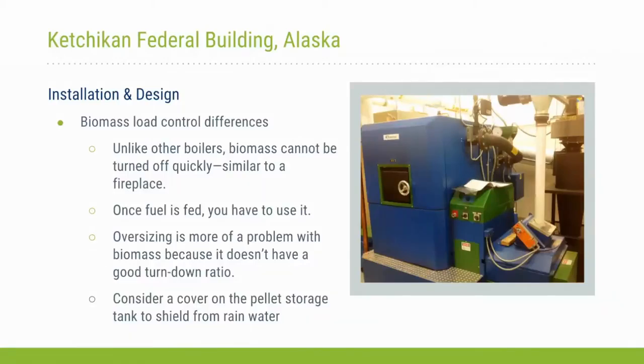And that fuel continues to add heat into the heating system, which can easily overheat the heating hot water supply to the building. In essence, oversizing is more of an issue than undersizing. It's a lot easier to undersize a biomass boiler and have a backup boiler like a fuel oil boiler as a trim boiler that closes the gap between what you're providing and what you need to provide. And that to me would have been a lot better operation in the building and would have led to a better economic outcome out of this project.